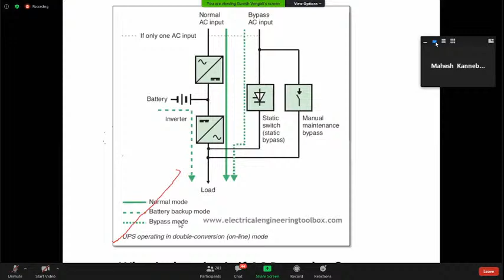So what is the criteria if AC power is lost? This is a question I faced. Some people say that if you lose AC power, immediately the battery will feed the load. Is that true? Or if you lose AC power, does the bypass energize? This is a general confusion, and you need to ask the vendor clearly what the criteria is if AC power is lost.